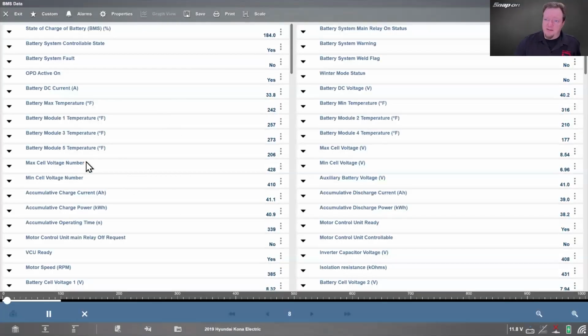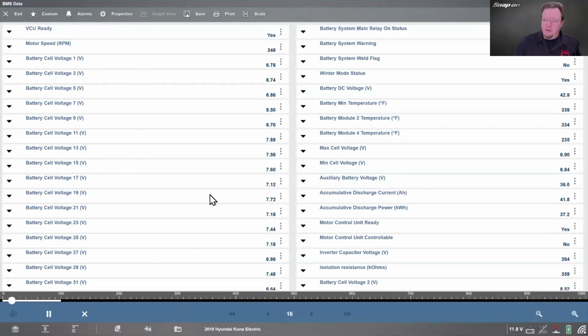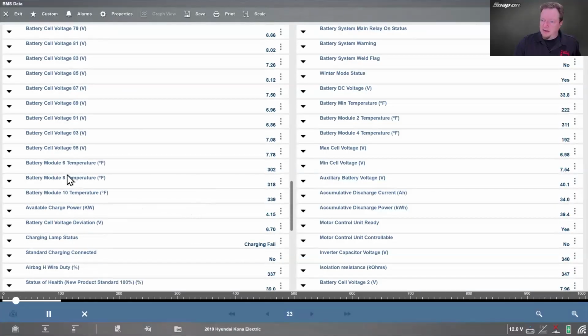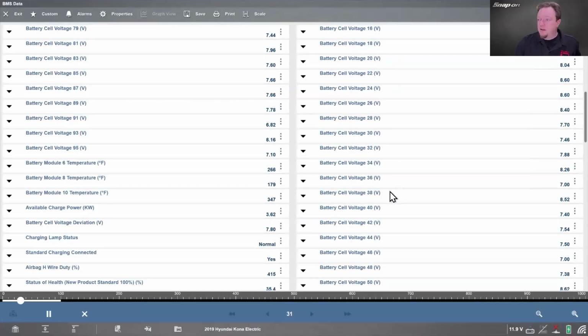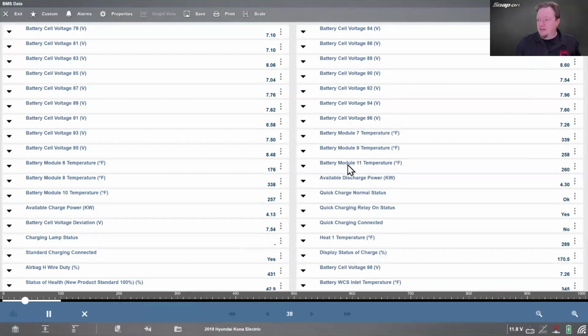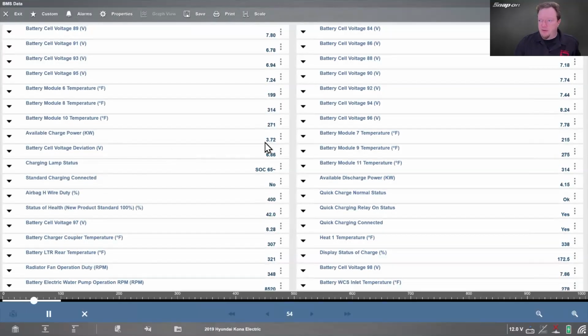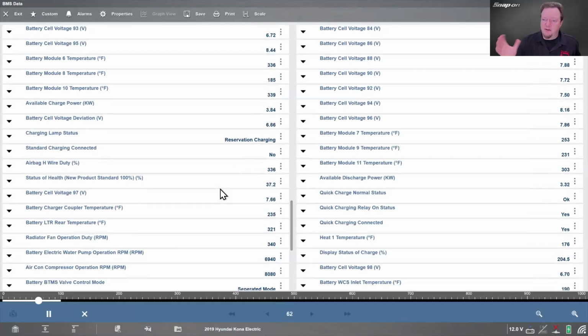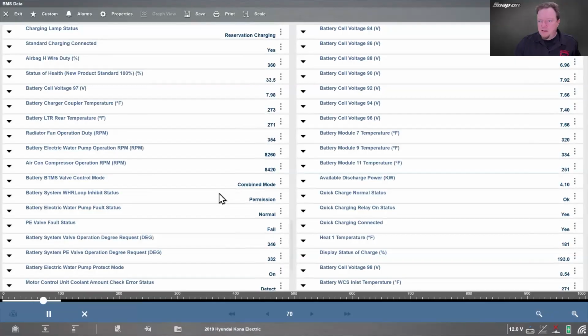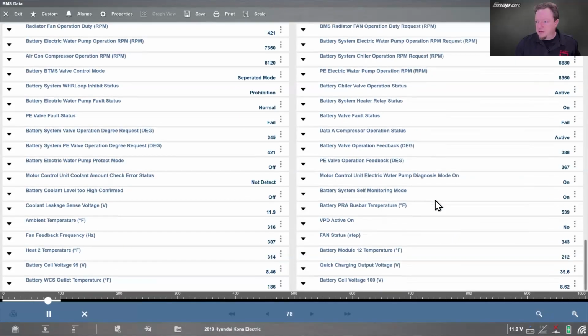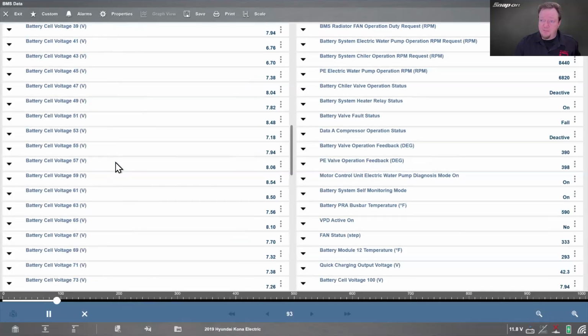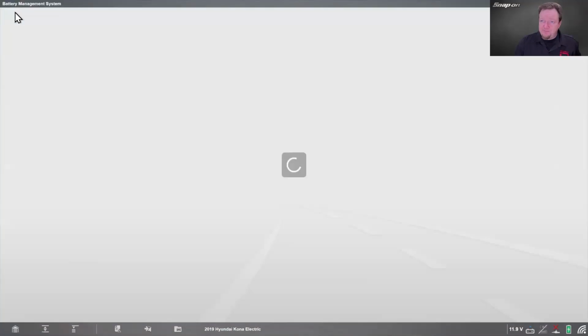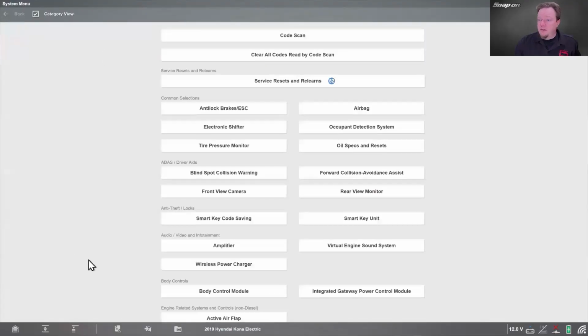Oh, as far as data, this one has data that's going to give you the max cell voltage, minimum cell voltage, and then your actual voltages per cell. In this case, we got 96, right? 96 batteries in different modules. Let's see, available charge power, cell voltage deviation. That's probably one you're going to want to look at to make sure there isn't too much deviation between them. Let's see, a couple other things in there. And you could print this out too. You could do a custom data list, or you could just print the whole thing out if you wanted to, save it for later, show it to a customer with that.